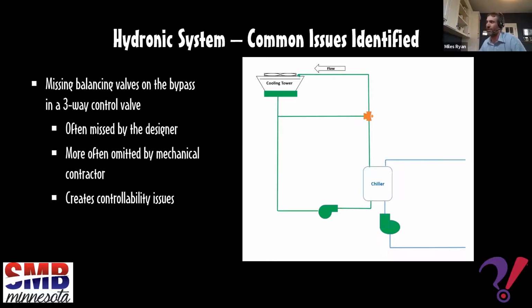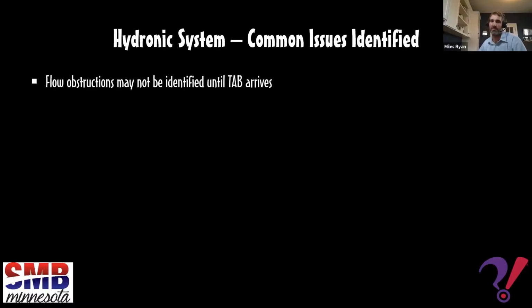You start tripping out chillers. And when you trip out a chiller in cold weather, now you're risking freezing water up in the cooling tower. It's just a whole host of nightmares that we've run into in recent winters because of a lack of a balancing valve placed in this line right here. All right, I'll get off my soapbox about balancing valves in the bypass line.